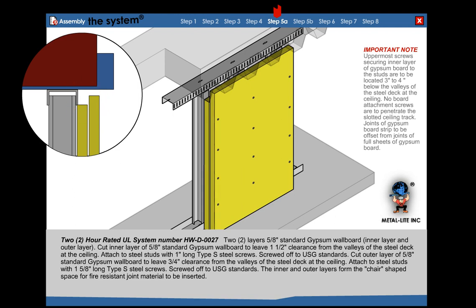Important note: Uppermost screws securing both inner and outer layers of gypsum board to the stud should be located 3 to 4 inches below the valley of the steel deck. No board attachment screws are to penetrate the slotted track.